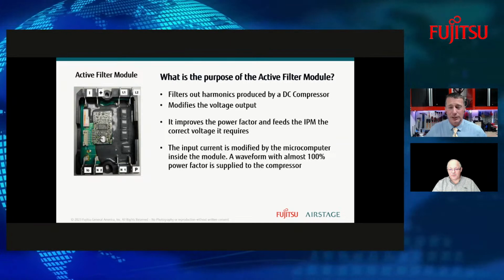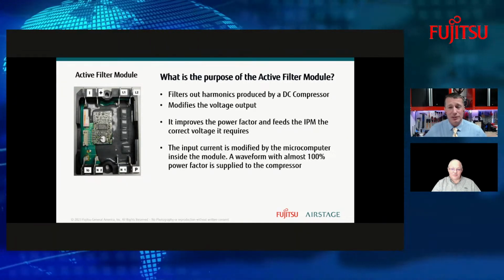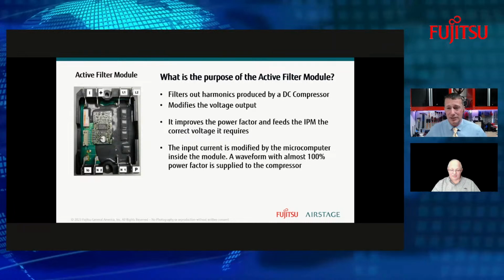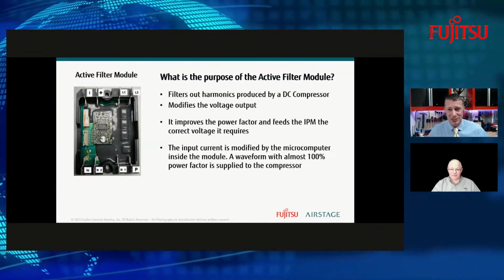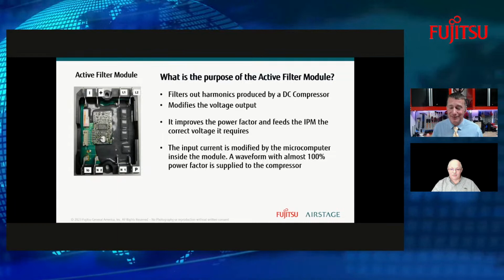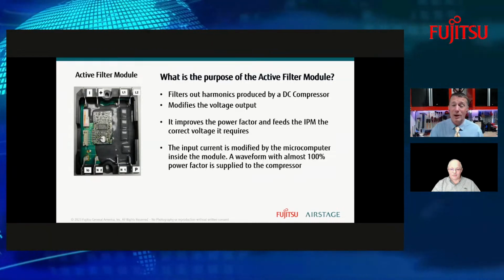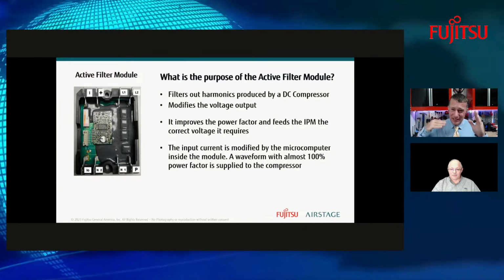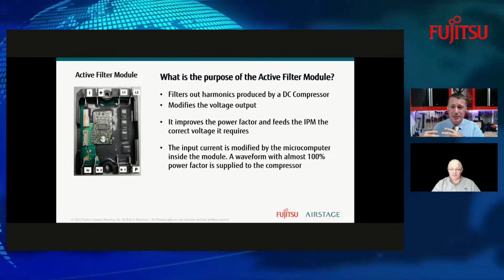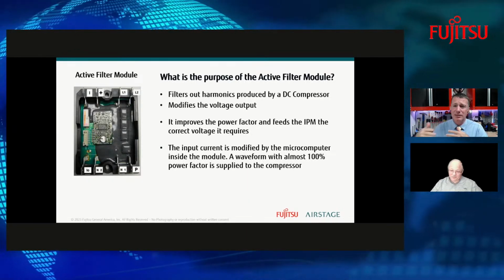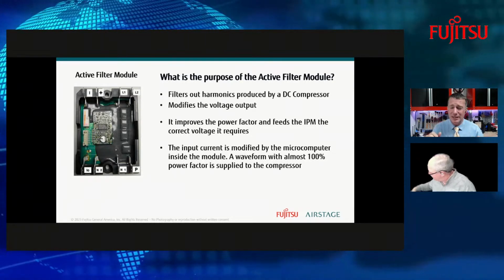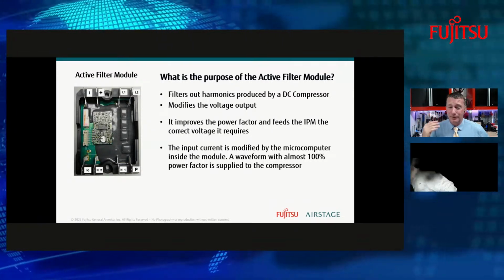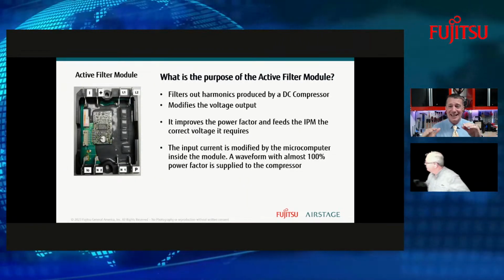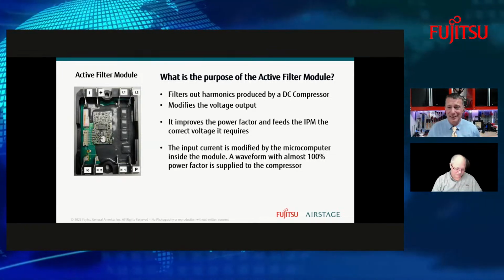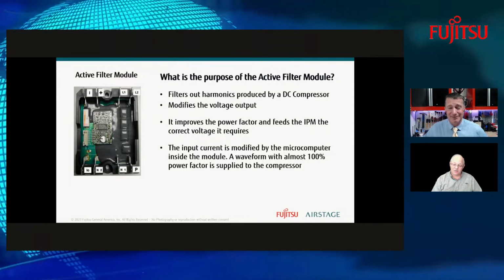I had one particular unit that would smoke a main control board every couple of months after installation. So the product itself was starting to get a bad reputation. When I went out and did the site visit and analysis on what we were actually seeing in the field, we were seeing some floating voltages. We had a new power distribution center put in half a block down, so we had some floating voltages while I was on site. After installing a voltage monitor on the system, all of our fluctuations disappeared, and none of my boards were having failure issues after that. So yeah, very important.